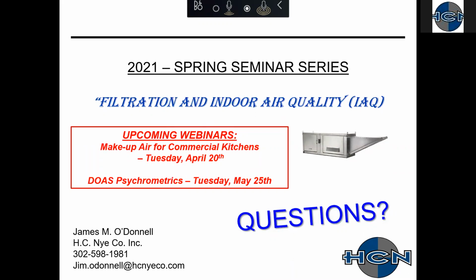Question from Dave Burkett: for BPI, can you measure the effectiveness in the space? What quantities of ions are desirable? You can measure the ions in the space. They do have handheld ion counters. It's sort of a loaded question, in that there hasn't really been any ionization quantities qualified.